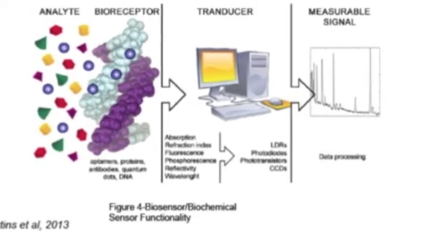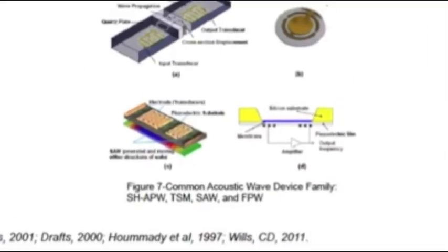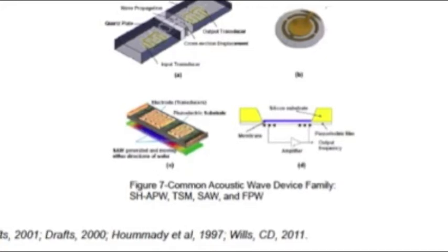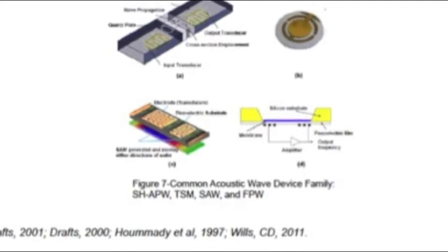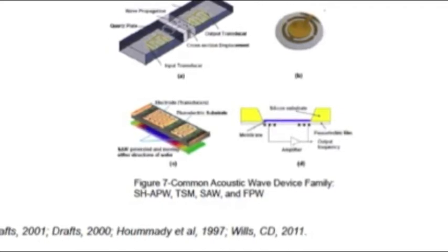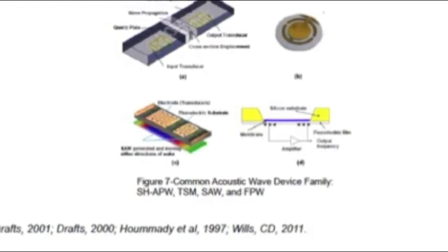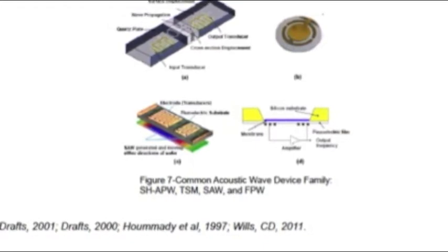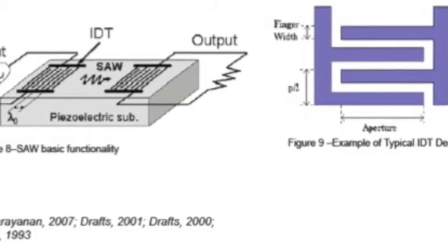The type of biochemical sensor I am designing and fabricating is an acoustic wave sensor. Acoustic wave devices are based on the use of elastic mechanical waves at frequencies well above audible range, traveling through specially designed solid sensing structures. The detection mechanism is the acoustic wave, which propagates through or on the surface of the material. Any variations in the propagation path can affect the velocity and/or amplitude of the wave. These changes to the velocity can be measured by monitoring the frequency and phase characteristics of the sensor. The frequency characteristics of the sensor in turn correlate to the physical quantity being monitored.